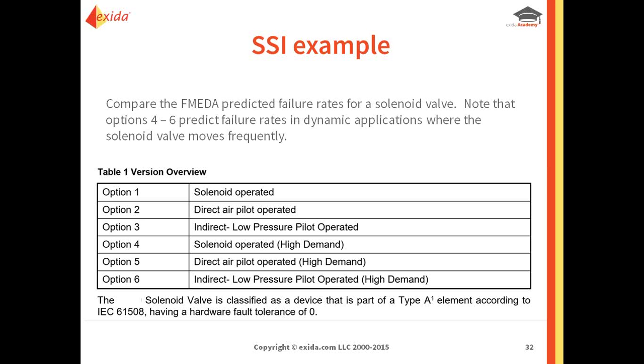And right here, you can compare the FMEDA predicted failure rates for a solenoid valve. Note that in this report, it says there are options 4 through 6, which are to predict failure rates in dynamic applications where the solenoid valve moves frequently. Okay, so those are high demand.